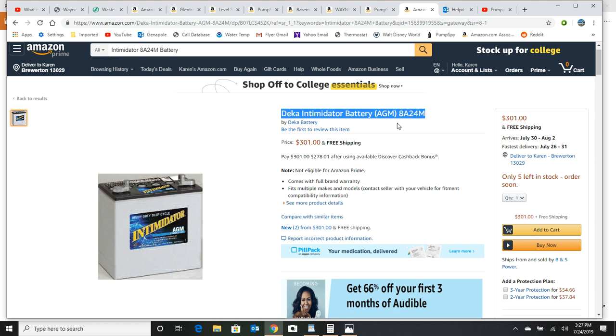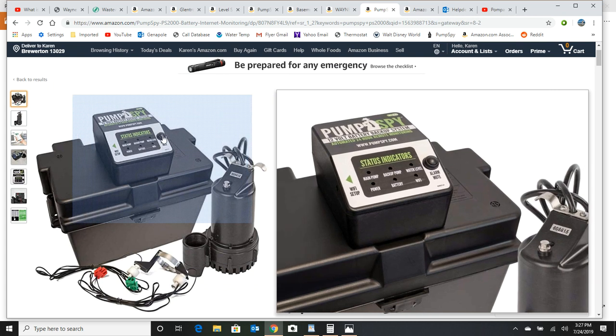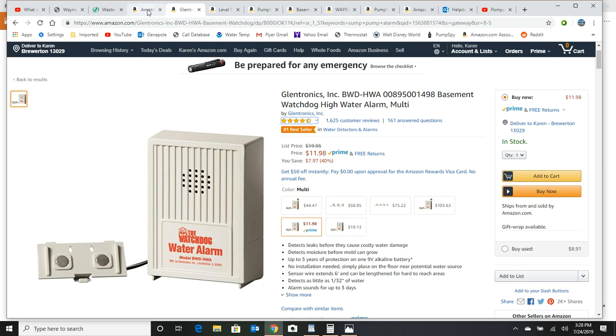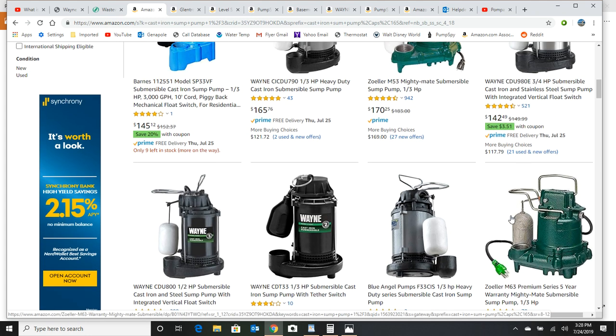Once you get all these pieces of the puzzle put together, when you're plumbing all this stuff, if you're not a plumber, make sure you follow the directions. The Zoeller pumps have a vent already built into them, but you also want to put a vent in your exit pipe too. It's really simple — you're just drilling a 3/16 inch hole in the plastic PVC pipe before you get to your one-way valves.